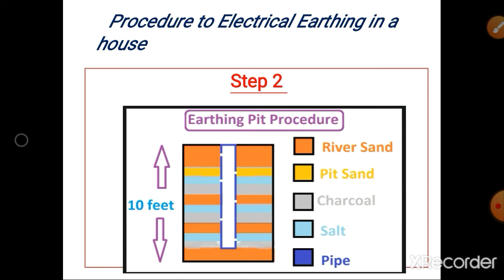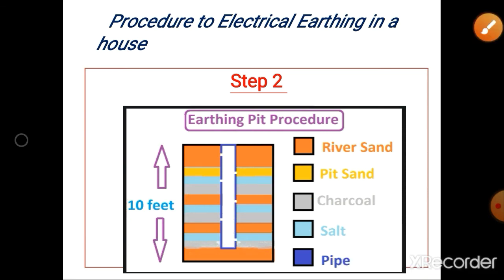In step 2, the depth of the pit is 10 feet, or 3 meters. After excavating the pit, the first layer is river sand, then we place charcoal, then a salt layer. After inserting the GI pipe, the gap is filled with alternate layers of sand, charcoal, salt, then sand, charcoal, salt, then pit sand, then river sand. After putting these layers, the combination is filled up to the clamp level, and we pour water into the pit.